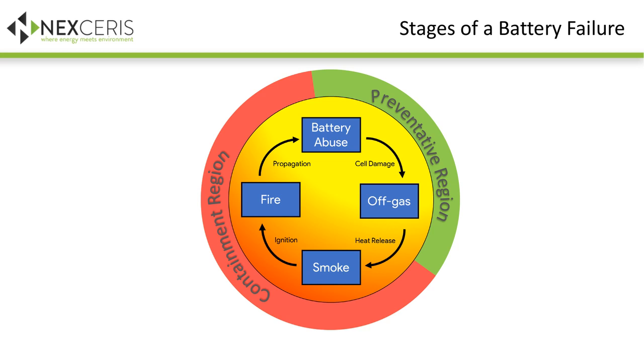If you start at the 12 o'clock position on this chart, it starts with battery abuse. This can be anything, including electrical abuse, mechanical abuse, physical abuse, or thermal abuse of the battery. This is going to result in some kind of cell damage, and at the 3 o'clock position those cells will vent and there's an off-gas release. If the cell continues toward failure, you get a heat release associated with smoke and fire, and that's the point recorded in the UL 9540A standard, where the surface temperature at thermal runaway is recorded.